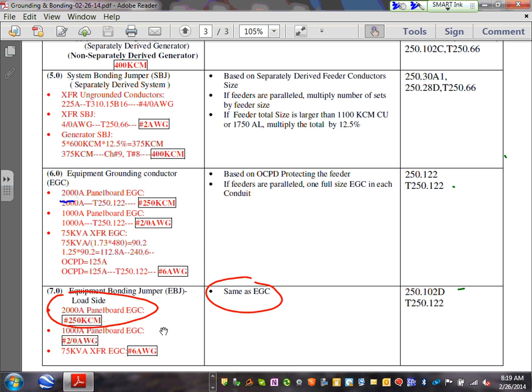So what does that mean, though? Here are 2 conduits, guys, coming to the second panel, and the conduits are coming from the bottom. You take a wire from conduit 1 to conduit 2 to the ground bar inside the sub panel. These are called equipment bonding jumper load side. Any comments, any questions about equipment bonding jumper load side? Karen?